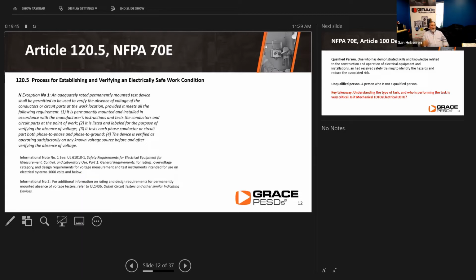Informational note 2 talks about UL 1436, which is for outlet circuit testers and other similar indicating devices. And the reason that these other products were slotted into this category is they didn't necessarily match everything under a UL 61010 environment, but they did match the requirements under the outlet circuit testers and other similar indicating devices. And it's actually added further technology into the lockout tagout procedure and creates an opportunity to continue to evolve how that lockout tagout procedure takes place.